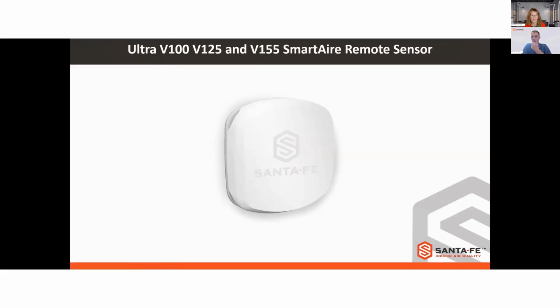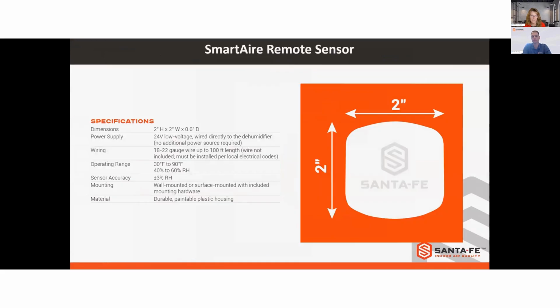And this is that new remote sensor that I had talked about. This will work with the V100, the 125, and the 155. And this is a SmartAire remote sensor that can be wired up to 100 feet from the dehumidifier. And as you can see here, it's about 2 inches by 2 inches. This can be placed in the living space, wired directly to the terminal block on the dehumidifier. And then on that digital onboard control, you can just set the relative humidity between 40 and 60%. And whenever this remote sensor senses that it is above whatever you have selected, it'll automatically activate that dehumidifier, and kind of keeps this bigger control out of the living space. It can be painted as well, and adds a lot of versatility on where it can be placed.